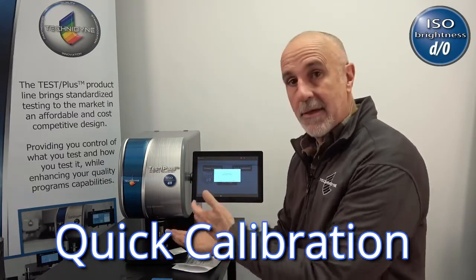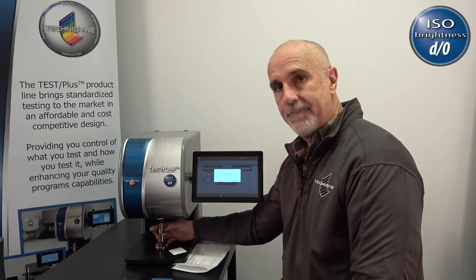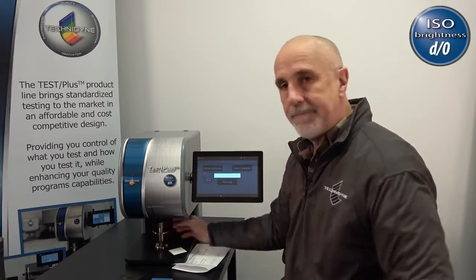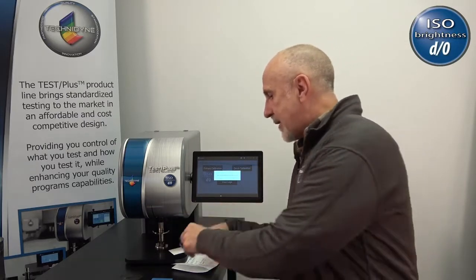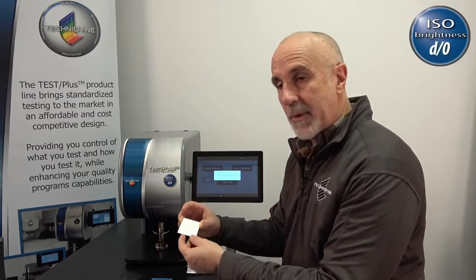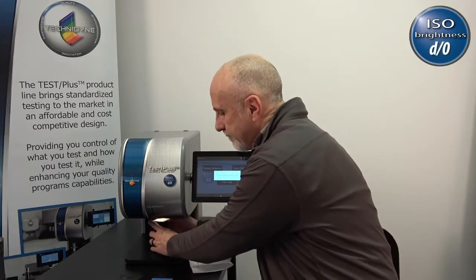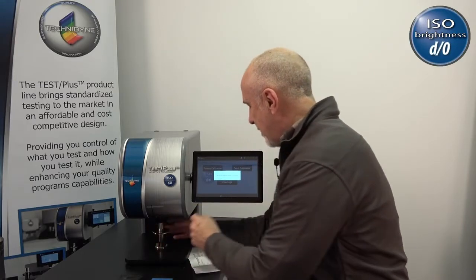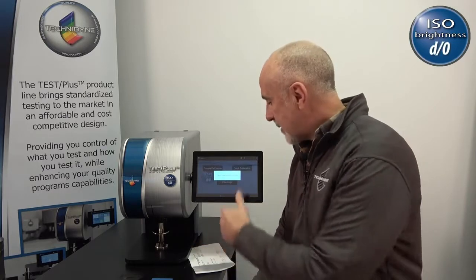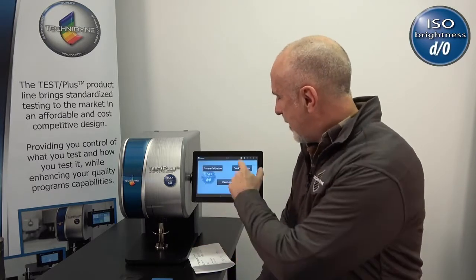Okay, the first thing it tells you to do is load the black cup and hit calibrate. I do that again, setting that low-level light reading. Once that's completed, it tells me to load the white working standard. Put that on there, select OK. It retrieves the value for that working standard, forces the instrument back to agreement on that, and completes that process. Yes, OK. Home screen, and I'm ready to measure again.